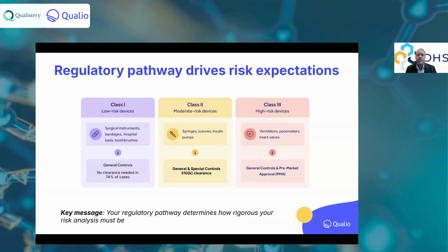So risk analysis now goes very, very deep. The solution there, by the way, in case you're curious, is to have redundant variables, so you do some best 2 out of 3 kind of thing in case something very unlikely happens. A cosmic ray hits your electronics and a bit is flipped. Nobody thinks about that. For mission critical, safety critical devices, you have to. Otherwise, even that one death is not acceptable, if it can be prevented.